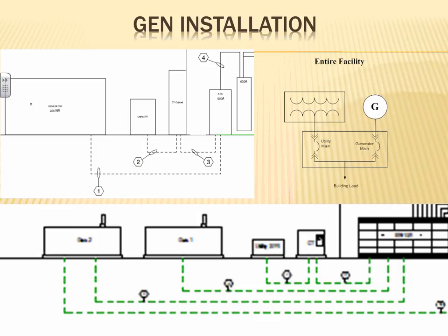But if you have a fixed circuit breaker, which is typically up to what, 200 amp, 225, once you go higher than 300 amp, you almost always want at least adjustable instantaneous, because it helps you with the motors, it helps you with a lot. Adjustable instantaneous is a big deal. Thank you. It's not as easy as it looks. If your circuit breaker is fixed, the coordination could be misleading.